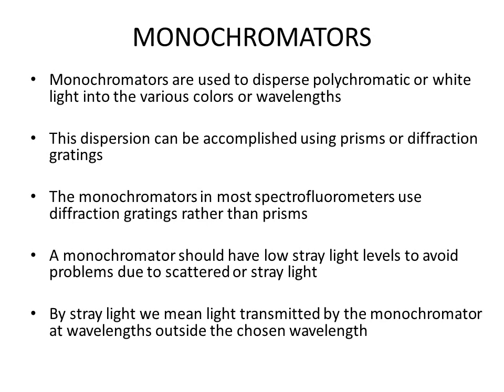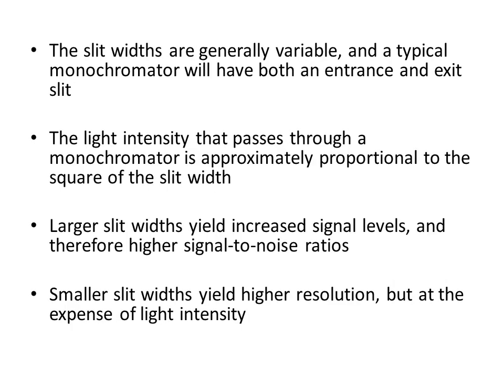The efficiency of a monochromator can be analyzed through its stray light level — it should have a low stray light level to avoid problems due to scattered or stray light. Stray light means light transmitted by the monochromator at wavelengths outside the chosen wavelength. You set your instrument at some wavelength, but the instrument also allows other wavelengths through — that radiation is stray light. The slit widths are generally variable.